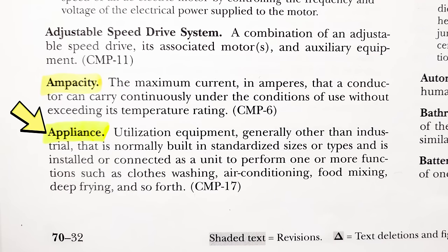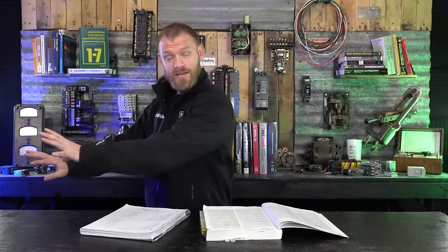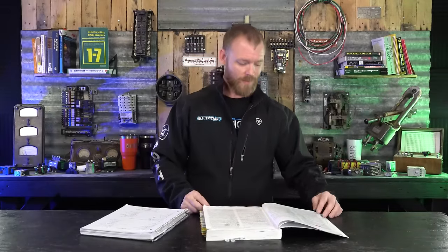Now, what is an appliance then? An appliance, it is utilization equipment, generally other than industrial, that is normally built in standardized types and sizes, and is installed or connected as a unit to perform one or more functions such as clothes washing, air conditioning, food mixing, deep frying, and so forth. So an appliance is generally something that's manufactured, right? Like a refrigerator is manufactured, it's got a cord on it. You buy it, you bring it in, you plug it in. It's not part of the premises wiring system. It's something you bring in and plug into the premises wiring system. And it's usually a pre-manufactured kind of thing.